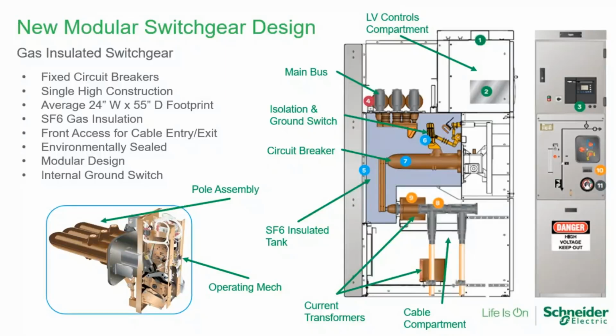With gas insulated switchgear designs, they're often front access only, so that the cable entries as well as the operating mechanisms are all in the front of the gear, and even installation can be done completely from the front of the gear. It uses a very modular design architecture, and when I say modular, I want you guys to think of basically switchgear Legos. If I need a main, a feeder, a tie breaker, I have a set architecturally designed cubicle to use as that style of operator, and I can build out my entire lineup basically by picking the types of cubicles I need and putting them together.